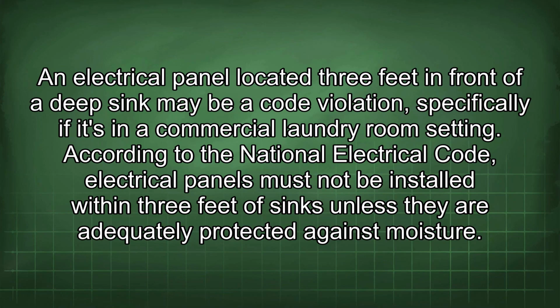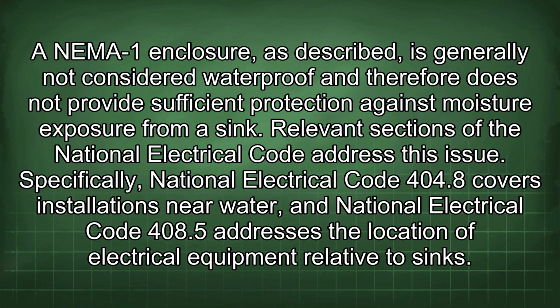An electrical panel located 3 feet in front of a deep sink may be a code violation, specifically if it's in a commercial laundry room setting. According to the National Electrical Code, electrical panels must not be installed within 3 feet of sinks unless they are adequately protected against moisture. A NEMA-1 enclosure, as described, is generally not considered waterproof and therefore does not provide sufficient protection against moisture exposure from a sink.